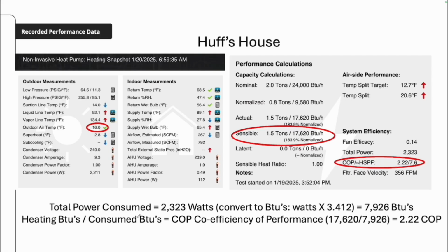So let me wrap this up by showing you what it looks like when you do this. This is actually my system. Don't worry about all that math at the bottom. This is a slide I use for the US Heat Pump Summit, just to kind of show how the COP is actually calculated, but we don't worry about that right now. So outdoor air temperature at the time of this test was 16 degrees. Now, I actually entered this in because I had a digital thermometer right out by my outdoor unit, and I was able to see it through my window. And so I didn't want to go out at 16 degrees to put an air probe out there, but I did take an actual measurement with a very accurate digital thermometer that was outside.